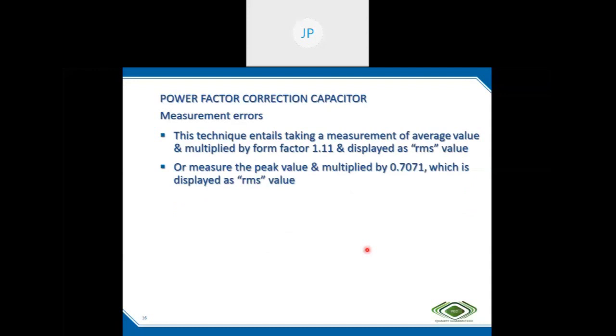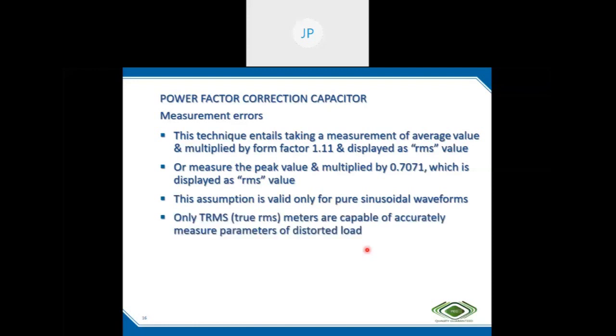So another method is peak value. We know peak by RMS value is root 2. So if you measure the peak value and multiply by 1 by root 2, that is 0.707, it is displayed as the RMS value. This assumption is not true for a distorted waveform. It is only true for a pure sinusoidal waveform. So only TRMS meters are capable of accurately measuring distorted waveforms.